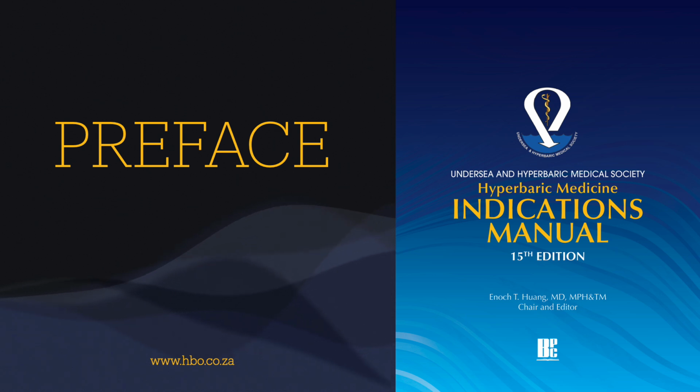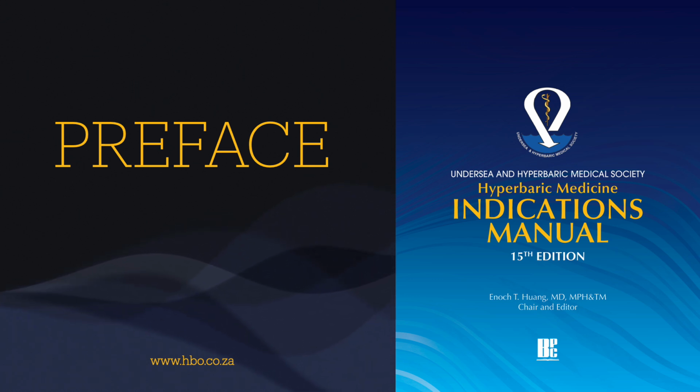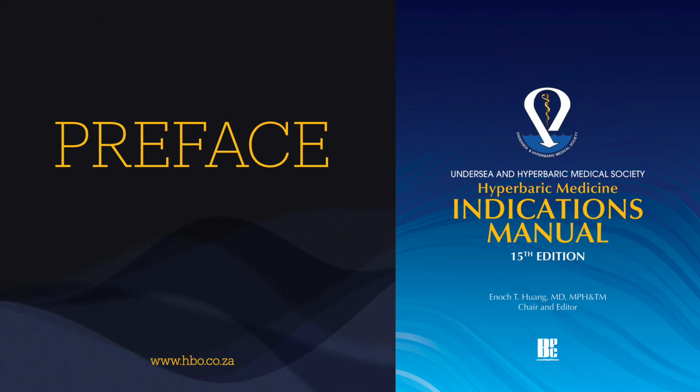Exactly. Now, the manual does include an important note. Class B monoplace chambers can also be pressurized with compressed air while the patient breathes near 100% oxygen using a mask or hood. So a monoplace isn't always filled with oxygen. It's not strictly required. It can be run with air pressurization and a patient mask or hood, similar to the setup in a multiplace, although the vast majority of monoplace chambers operate with the chamber filled with 100% oxygen. The manual also briefly mentions and shows an image of a Class C animal chamber, just noting it's for animal studies, research, not human clinical use.